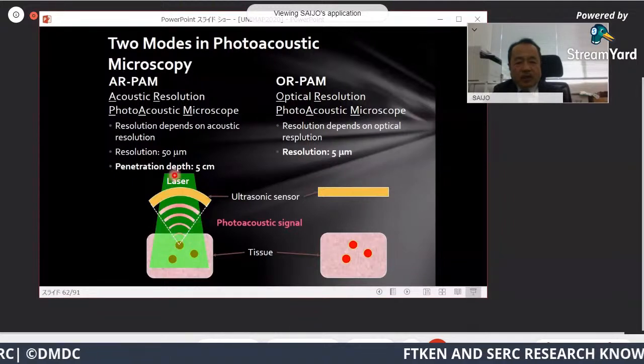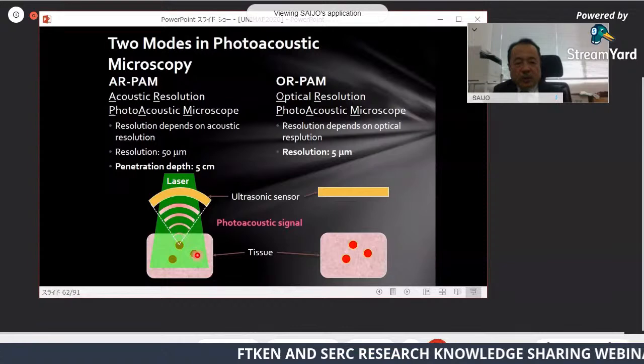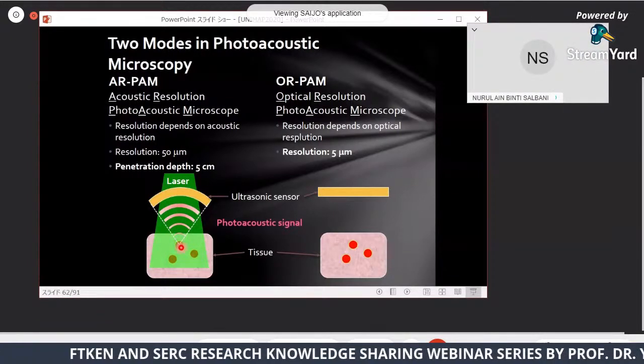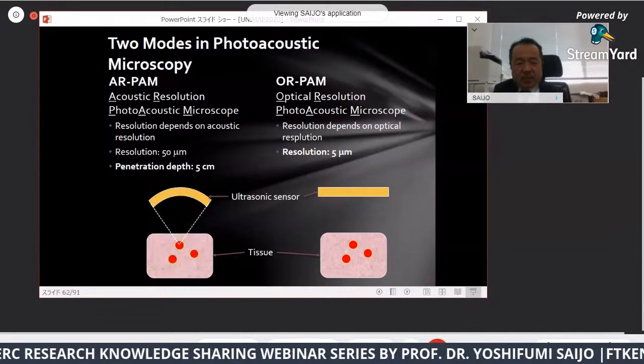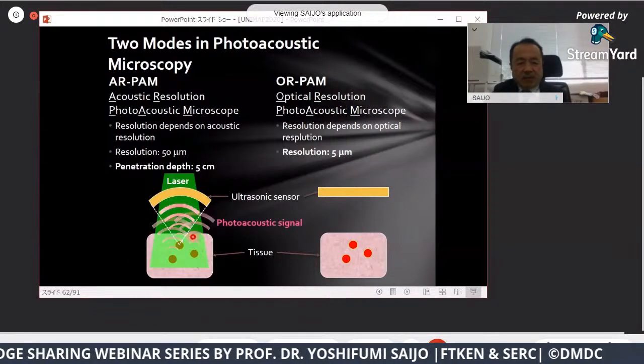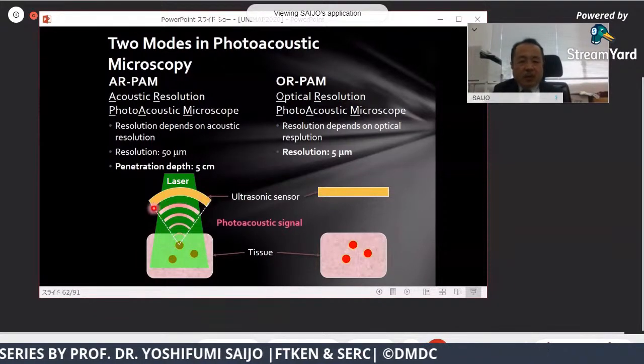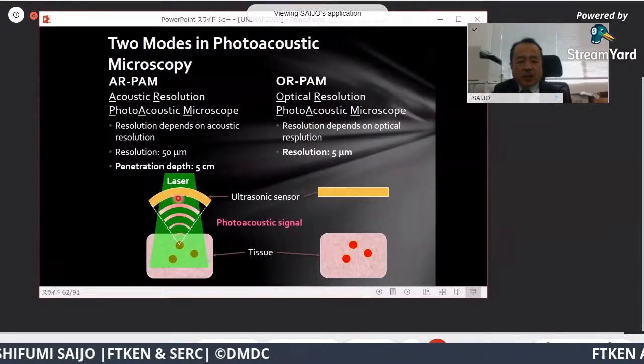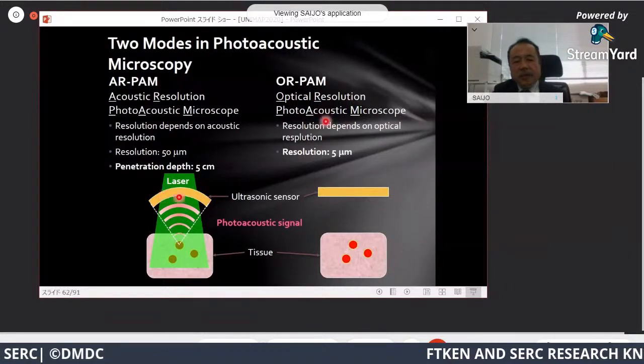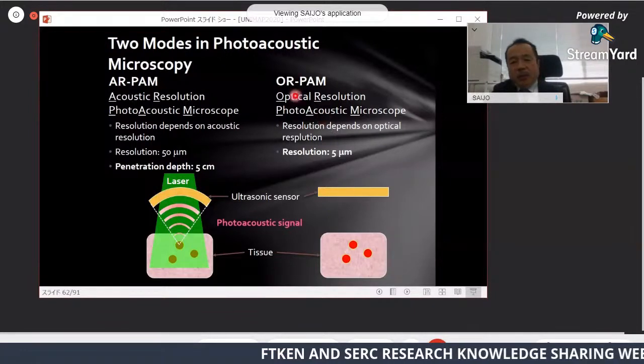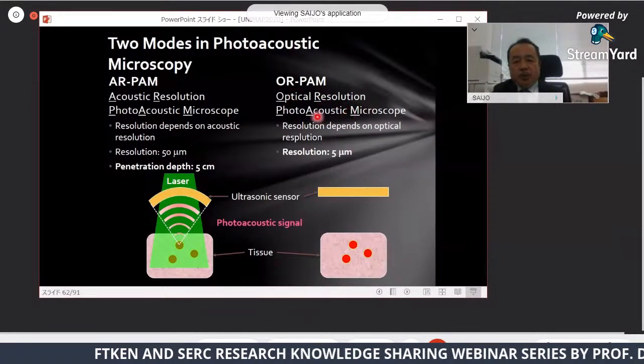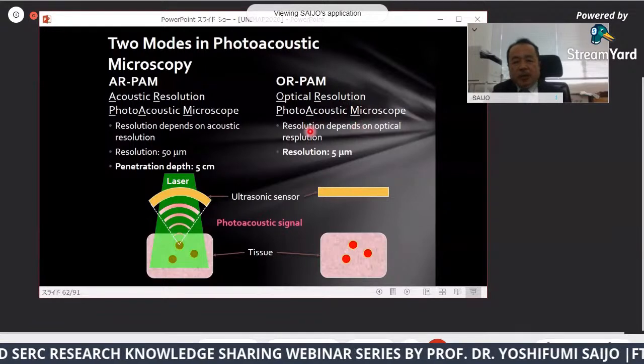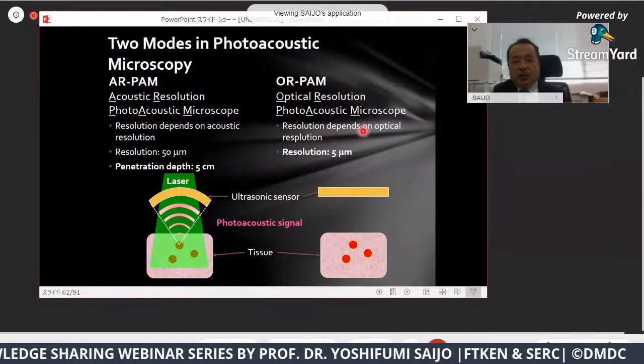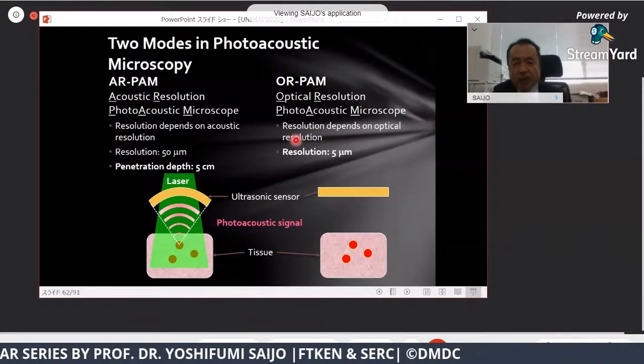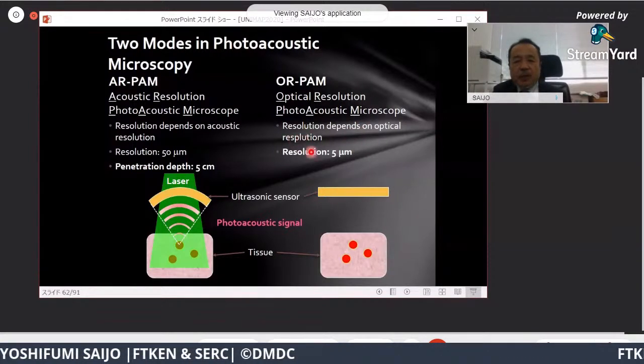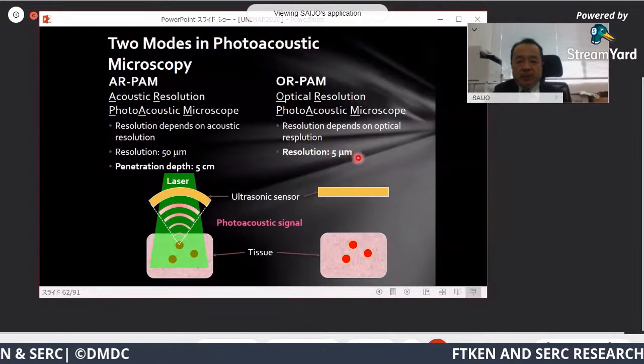So laser is irradiated to the whole tissue. Then each target makes some sound. And now this is a microphone, so we can obtain the photoacoustic signal by this. And talking about the OR-PAM, this is the optical resolution photoacoustic microscope. In this case, resolution depends on optical resolution, and the resolution is almost 5 micrometers.